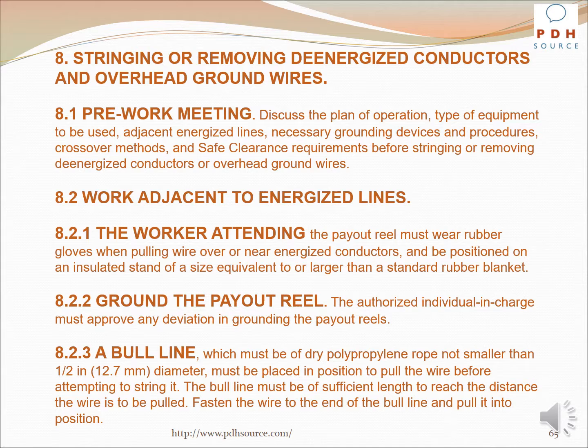Work adjacent to energized lines. The worker attending the payout reel must wear rubber gloves when pulling wire over or near energized conductors and be positioned on an insulated stand of a size equivalent to or larger than a standard rubber blanket. Ground the payout reel. The authorized individual in charge must approve any deviation in grounding the payout reels.